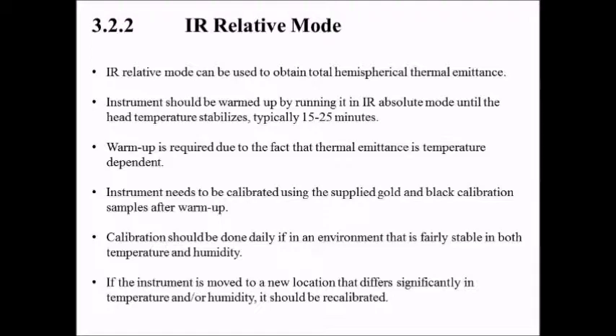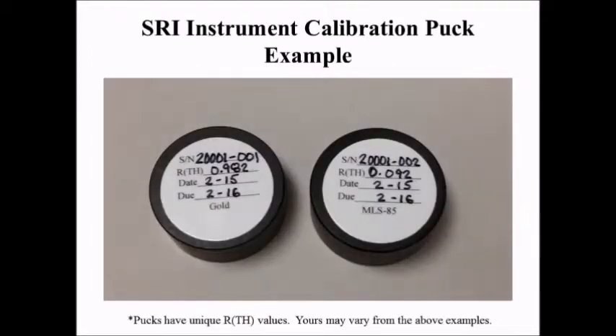Calibration should be done daily if in an environment that is fairly stable in both temperature and humidity. If the instrument is moved to a new location that differs significantly in temperature and/or humidity, it should be recalibrated. Calibration pucks have unique calibration values. Yours may vary from the above examples.